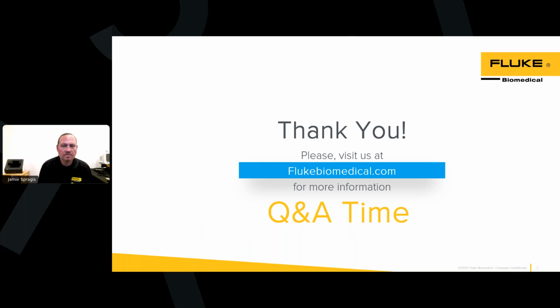Another question we had is, what are the main differences between this model and the ESA612? Good point. So the ESA612 and the 712 are very comparable, whereas with the ESA715 and 615, the 615 does differential leakage where the 715 doesn't. The reason we didn't do that is we wanted to make it small and portable. So if you needed differential leakage, then you would have to go up to our 620. But with size and portability, the 715 and 615 do a lot of the same electrical safety standards. They're just configured a little differently within the instrument, and in size and portability.